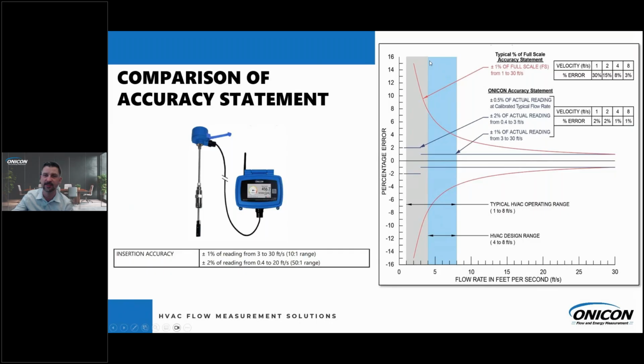But let's look at the accuracy at the velocities that we're typically seeing. In closed loop systems, chilled water, hot water, condenser water, it's typically around 4 to 8 feet per second. At 4 feet per second, that 1% of full scale device is actually plus or minus 8%, while we're maintaining 1% over that entire range. And then what about domestic water, when you're trying to measure a sink running, a toilet flushing, a shower going? Those domestic water or makeup water applications can be down to 1 foot per second. At 1 foot per second, that 1% of full scale device is plus or minus 30%. We're maintaining 2% at the low end.